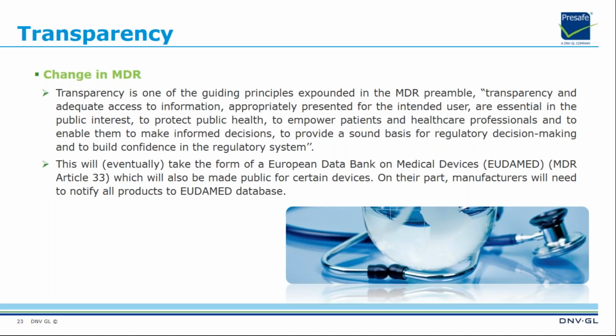This will eventually take the form of a European data bank on medical devices called EUDAMED, based on Article 33 MDR, which will also be made public for certain devices. On their part, manufacturers will need to notify all products to the EUDAMED database. Manufacturers should closely follow the continuing evaluation of the EUDAMED system and prepare for its implementation so as to be able to notify all products to the European Data Bank medical device database.